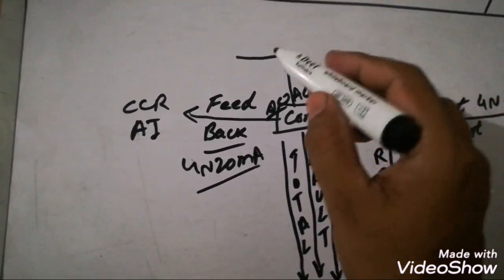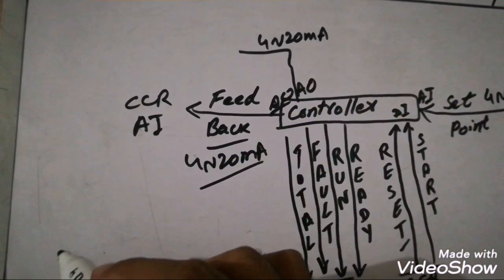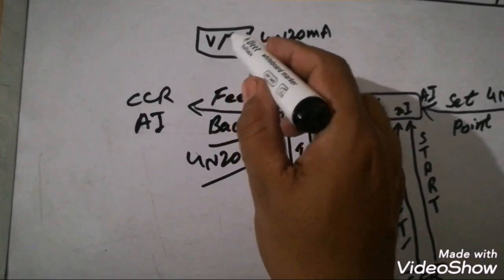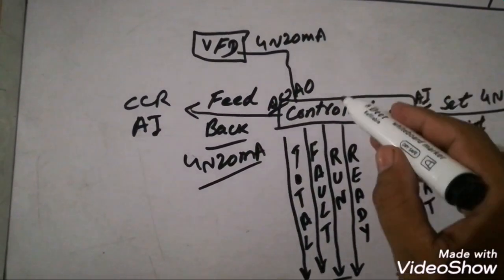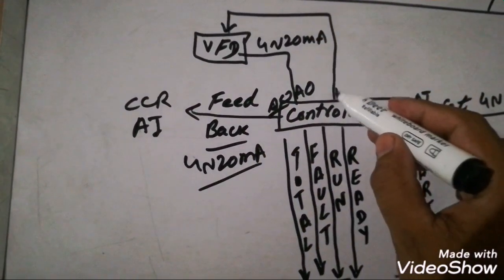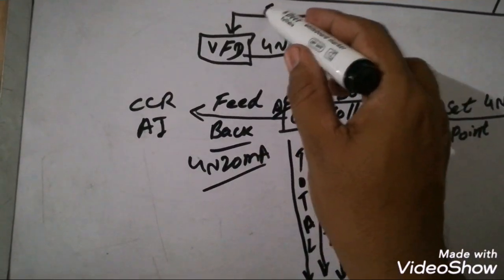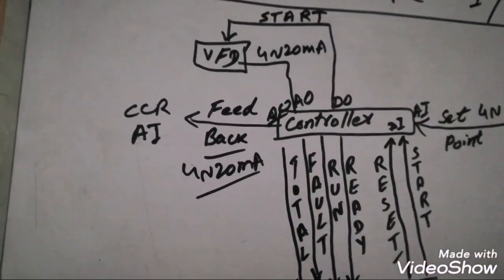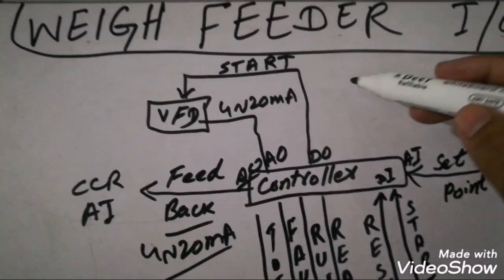Another analog output of the controller is the input to the VFD — this is 4 to 20 mA and is the set point to the VFD indicating how much speed is required to meet the CCR set point. There is also a digital output for the VFD which is the start command — when the operator starts the weigh feeder, the controller generates a start command to the VFD and the motor is started.